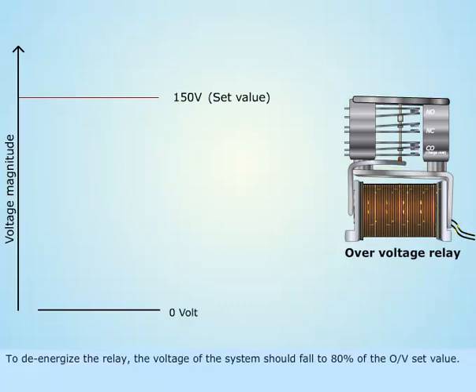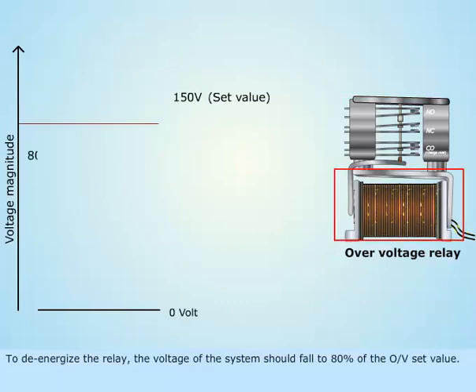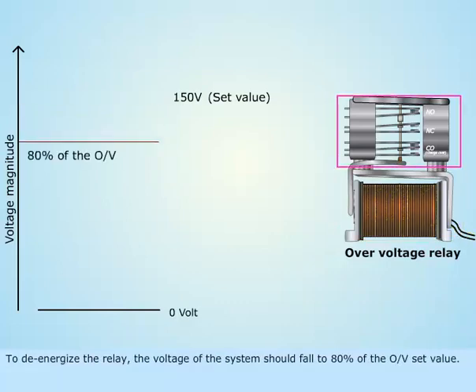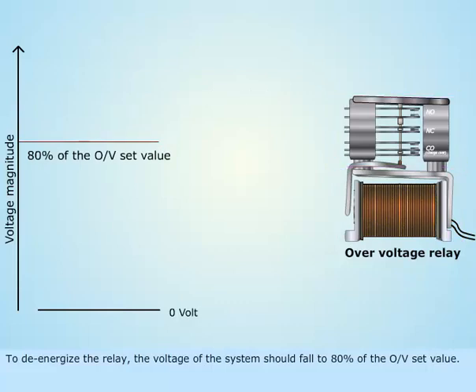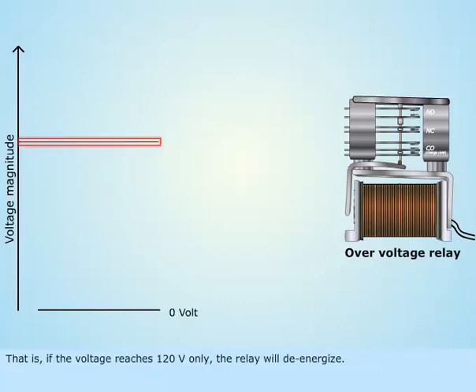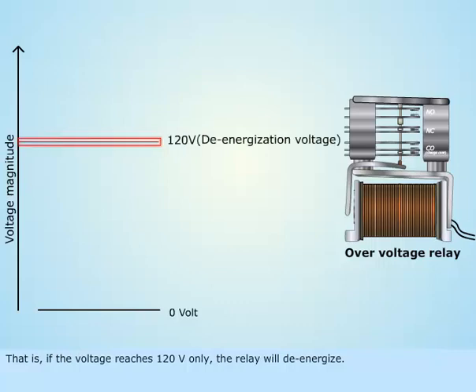To de-energize the relay, the voltage of the system should fall to 80% of the over voltage set value. That is, if the voltage reaches 120 volts, the relay will de-energize.